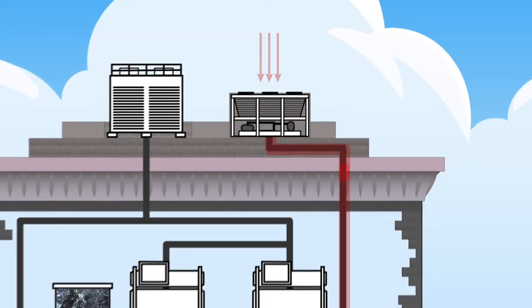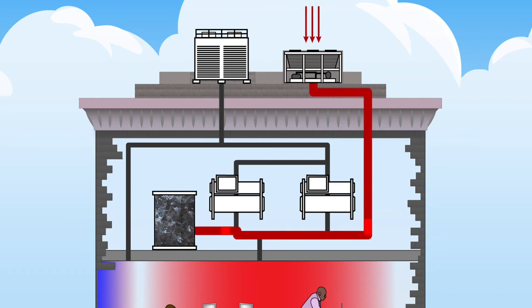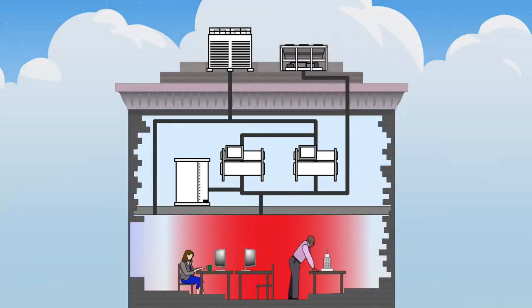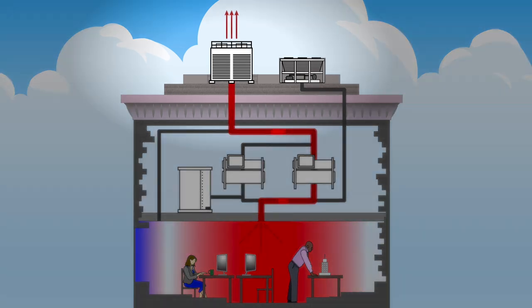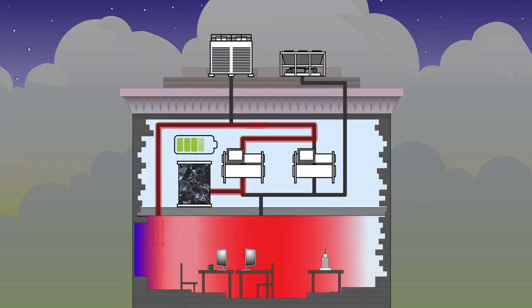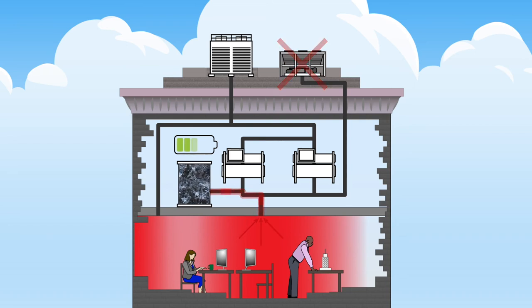You may be thinking: what do we do when the ice tanks are frozen solid, when the thermal battery is empty and there's no more ability to give up heat? Well, we need to melt the tanks, and that can be done in two ways. First, you could fire up the air source heat pumps to bring heat into the building and melt the ice, but that takes a lot of energy. The better option has to do with the cyclical nature of loads in a building. There are many times a year when a building goes through heating and cooling cycles within the same day. On those days, we can use that extra heat that we would have rejected from the building to recharge the battery for free. In these cases, we like to say the building is able to heat itself. By using ice, you can leverage those cyclical loads quite often, reducing the need to fire up that costly air source heat pump to balance the load.